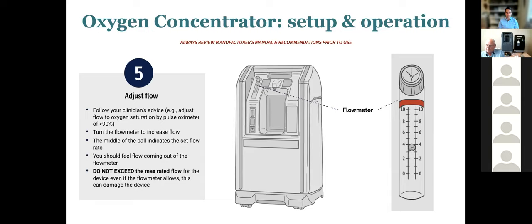A big take-home from this slide is to not exceed the max rated flow of the device, even though some flow meters will allow you to adjust them so that the ball in the flow meter will go above the max flow. Try to avoid doing that. That can significantly decrease the efficiency of the machine. It can also cause damage to the machines as well. So that's a big tip to avoid.